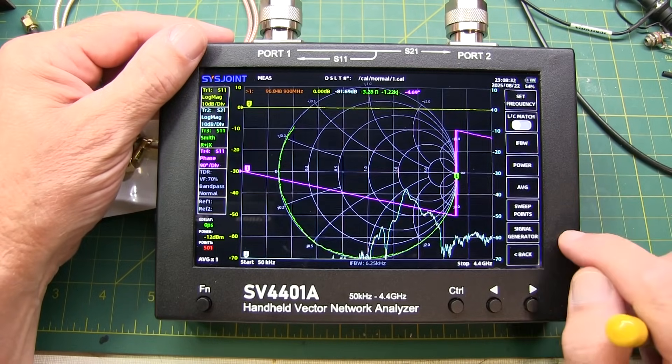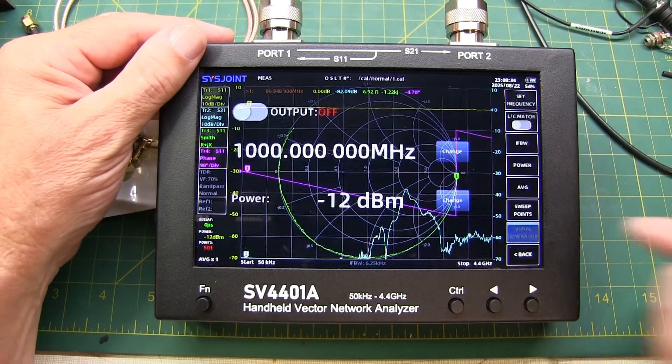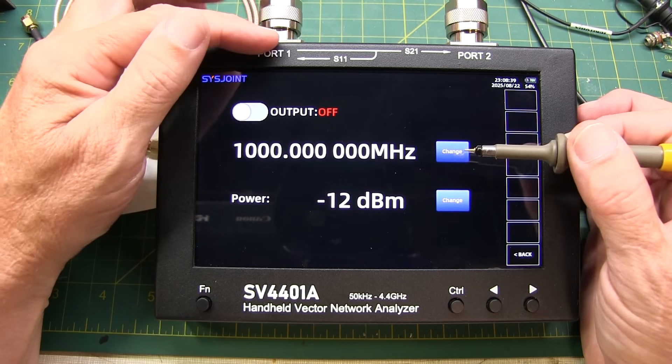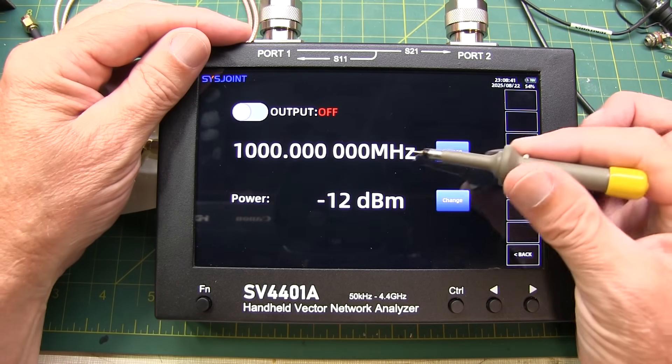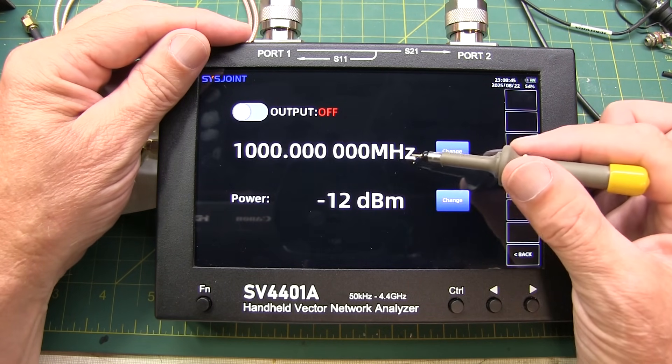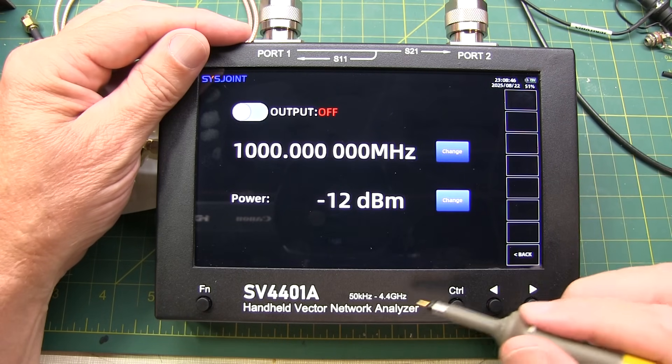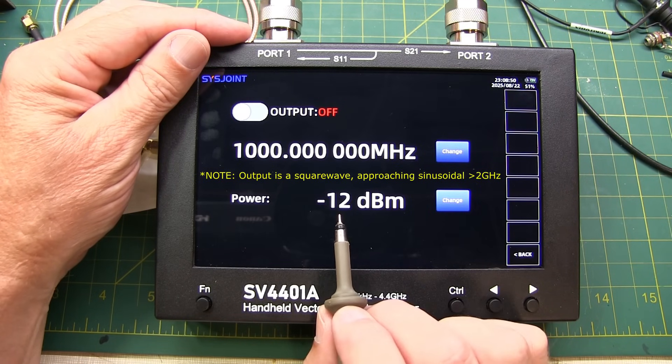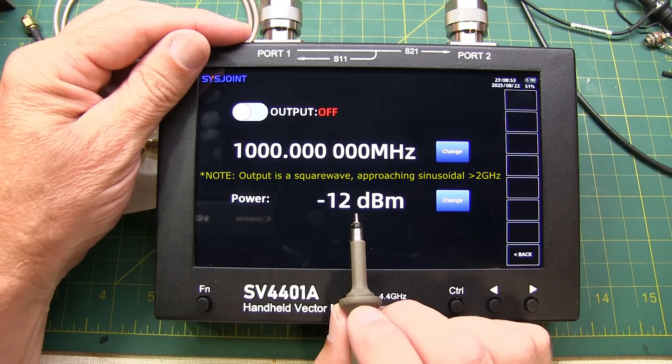And finally under the stimulus menu you can also go and set the signal generator mode. Now in this mode you can actually set the port 1 to be an RF signal source, essentially from 50 kHz to 4.4 GHz, the frequency range of the instrument, and power range again from about minus 42 dBm up to minus 12 dBm.